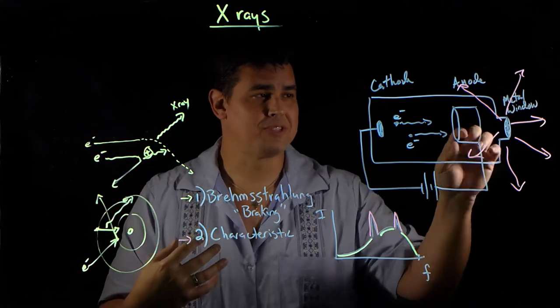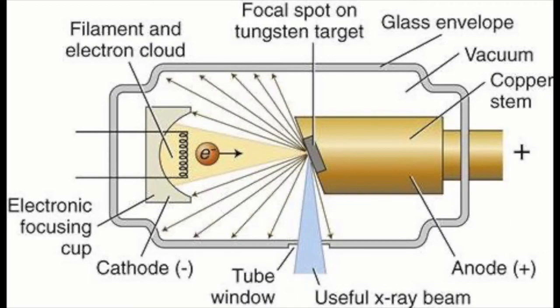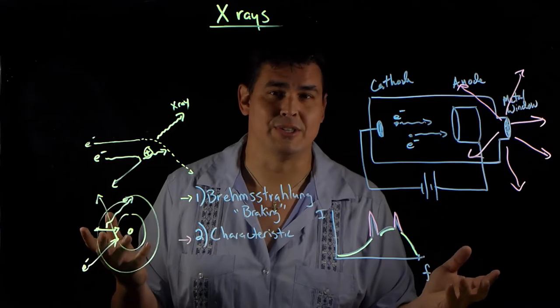So nowadays what they do with x-ray tubes, instead of letting these x-rays fly everywhere, they take the tube and encase it in lead and they have an opening so that x-rays will only come out the bottom so you can direct the x-rays, so people aren't just getting exposed to x-rays all over the place.